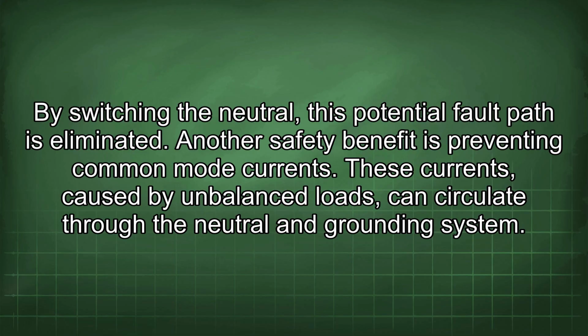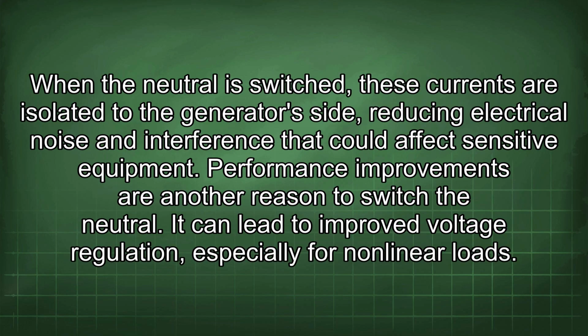Another safety benefit is preventing common mode currents. These currents, caused by unbalanced loads, can circulate through the neutral and grounding system. When the neutral is switched, these currents are isolated to the generator's side, reducing electrical noise and interference that could affect sensitive equipment. Performance improvements are another reason to switch the neutral.